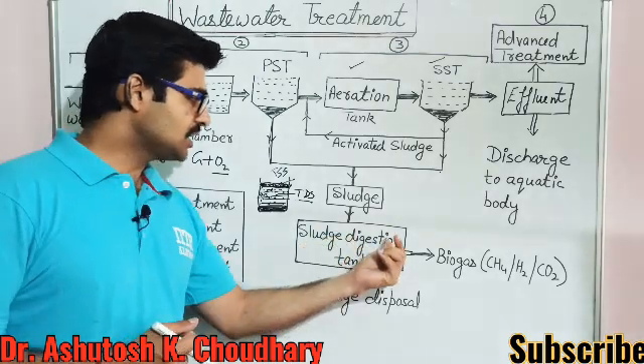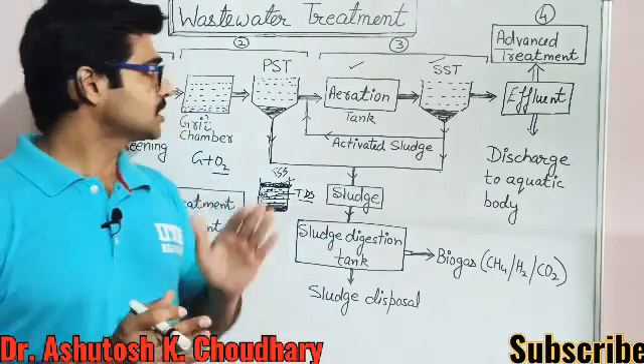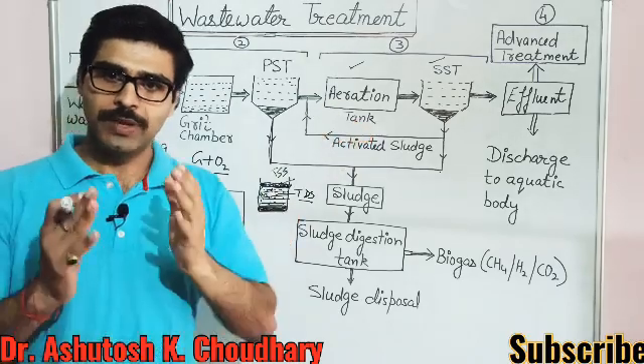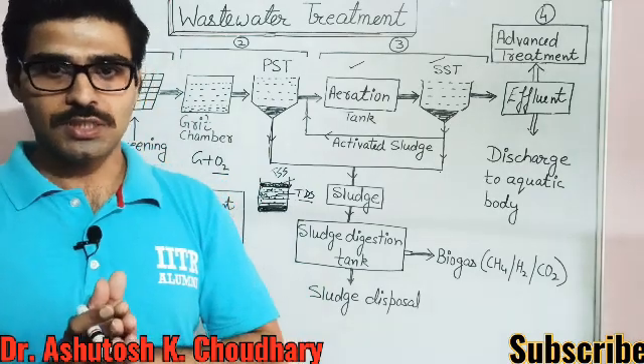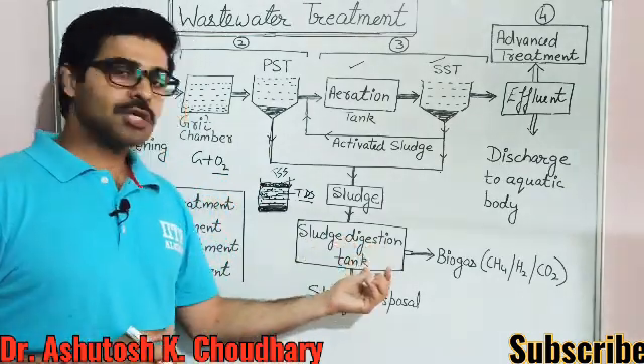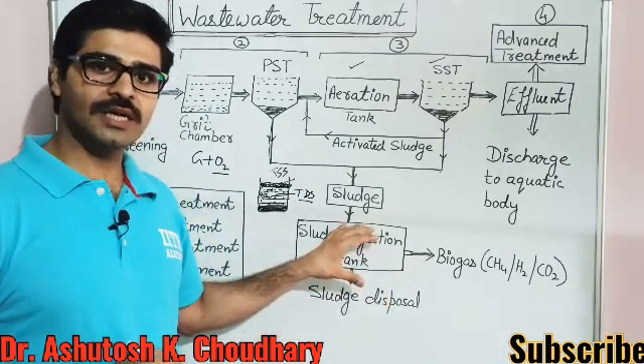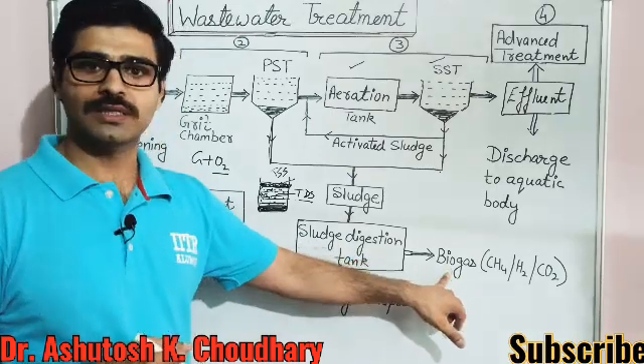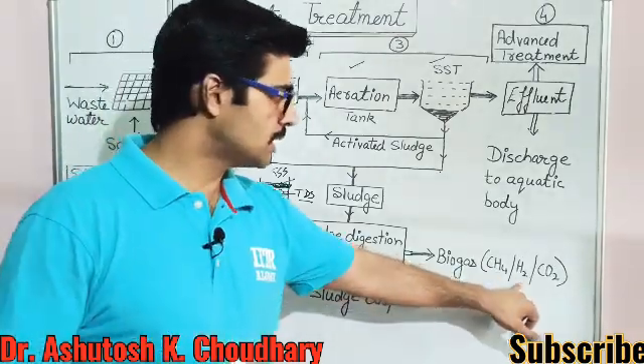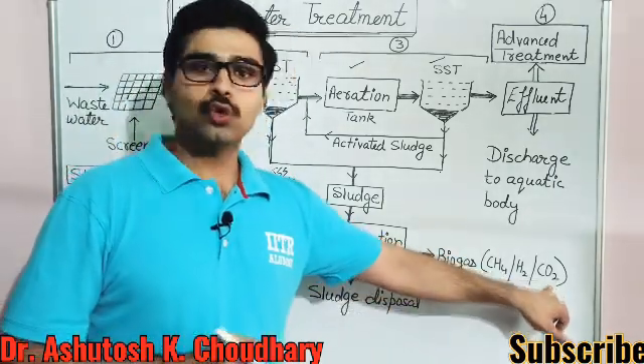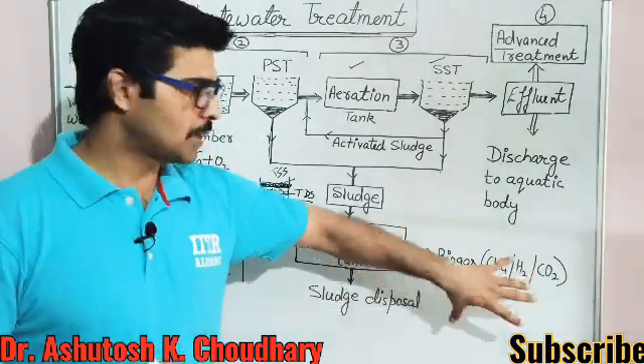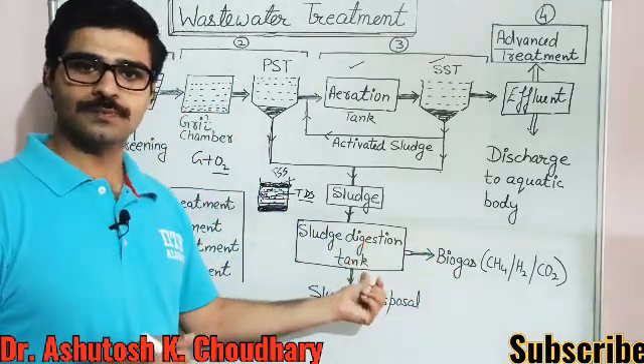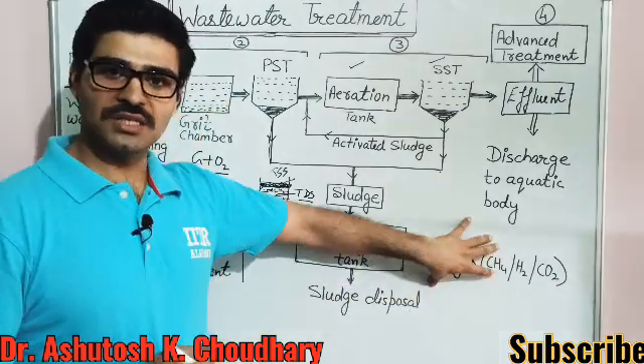The aeration process was aerobic because oxygen was involved — aerobic means bacteria oxidize pollutants in the presence of free oxygen. But the sludge digestion process is anaerobic. Anaerobic means bacteria degrade the sludge in the absence of oxygen and generate biogas — for example methane, some hydrogen, and CO2. This biogas can be used as fuel. Most industries in India use this sludge digestion process to generate biogas, recovering energy from wastewater.